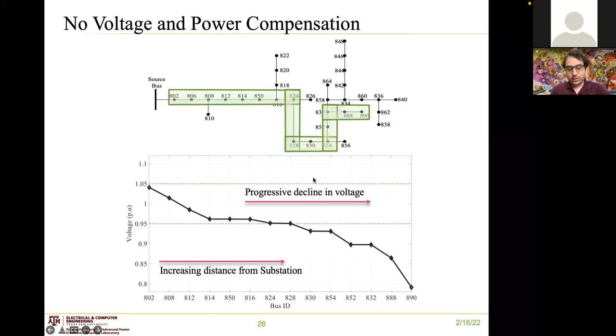And we can see that pretty soon we are having voltages that go outside acceptable limits. But when we connect these devices back at their optimal locations, we have an improved voltage profile. So for example, if you take a look at the first regulator that's connected between bus 814 and 850, we'll see that the voltage at bus 850 has increased. And as we move further along the length of this feeder, the voltages begin to drop until we hit the second regulator, which is connected between buses 852 and 832. And we see that the voltage is again increasing at the bus 832.